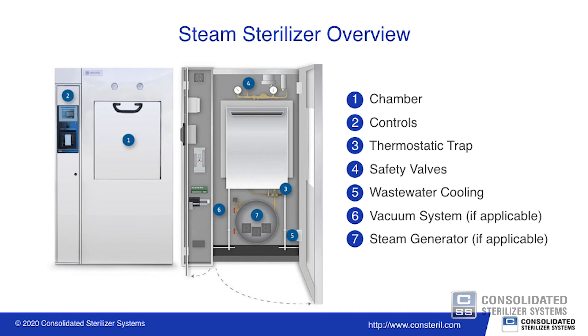Lastly, there is a wastewater cooling mechanism, which cools effluent — that is, air, steam, and condensate — before it enters the drain piping. An autoclave might also include a vacuum system, which enables the user to forcibly remove air from the chamber with a vacuum. And a steam generator or boiler, which uses electric heating elements to heat water and generate steam.